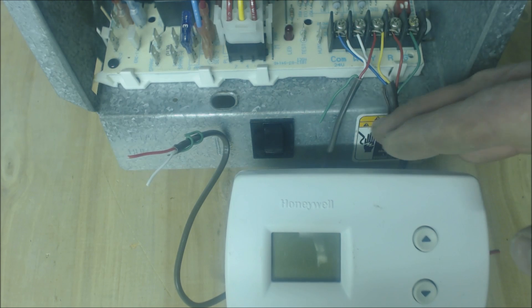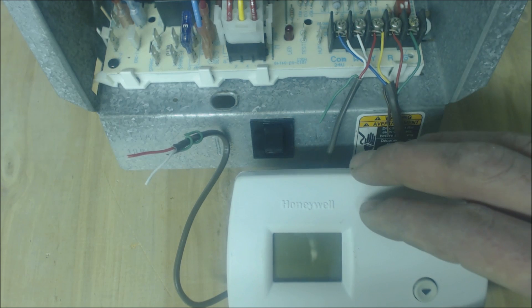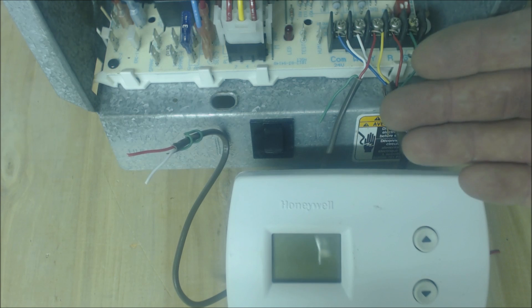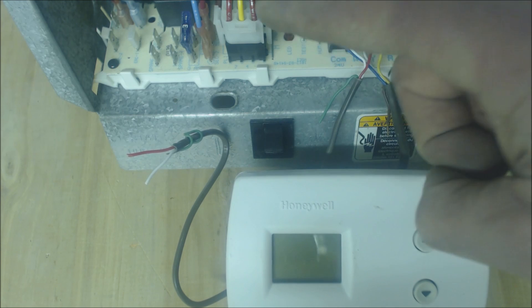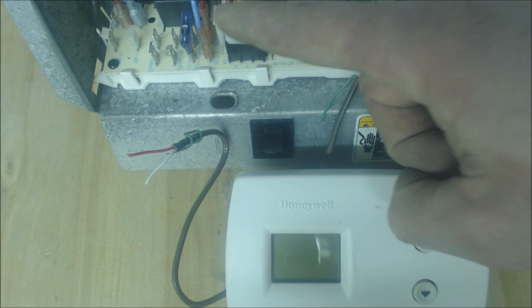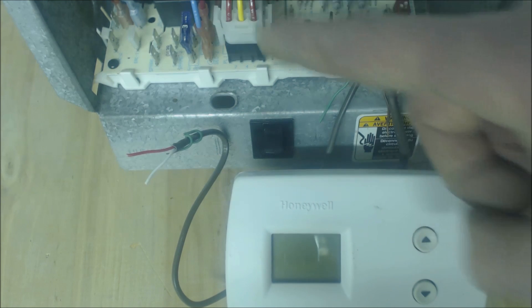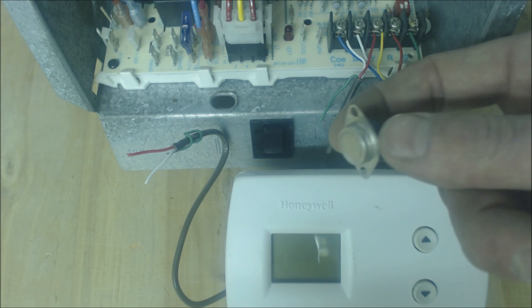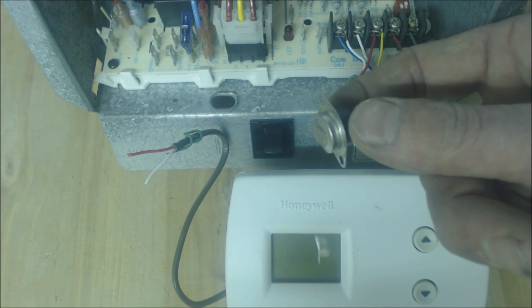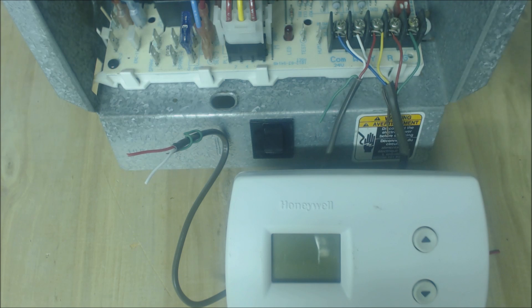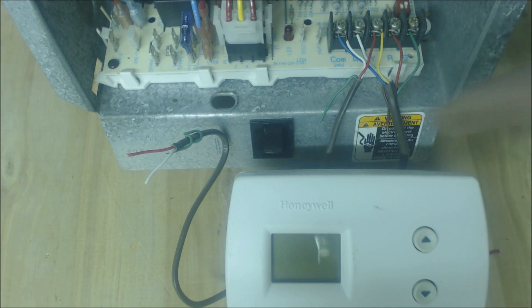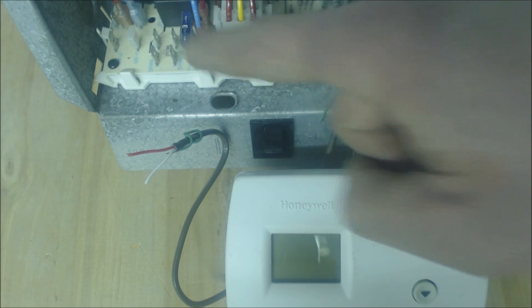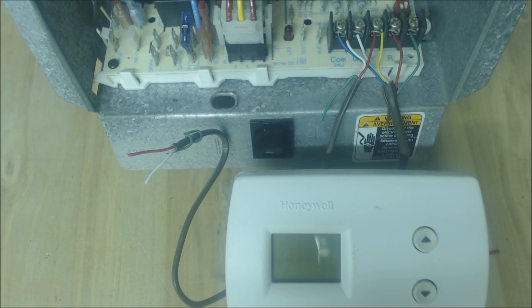Maybe in your thermostat wires, maybe in your thermostat itself, it could be that one of your 24 volt sensor wires going to say your flame rollout switch is touching the ground. So that's all things that could end up popping this 3 amp fuse.